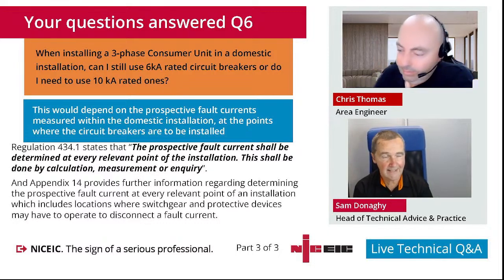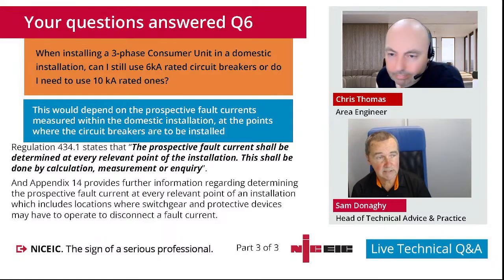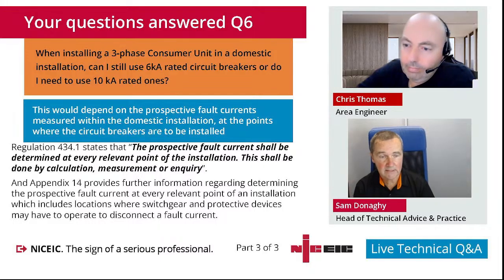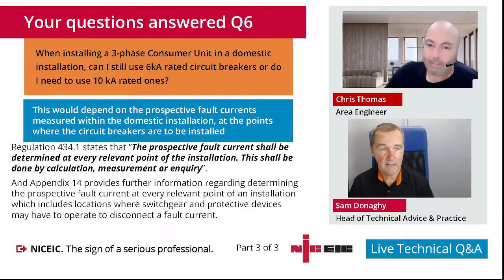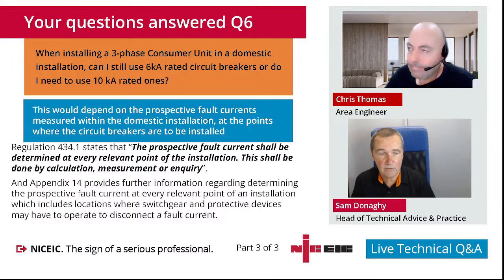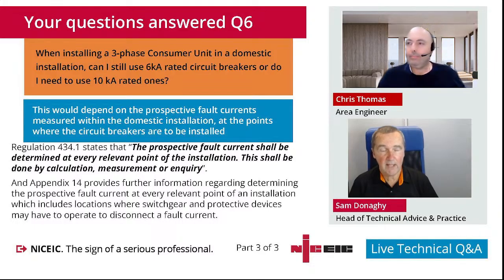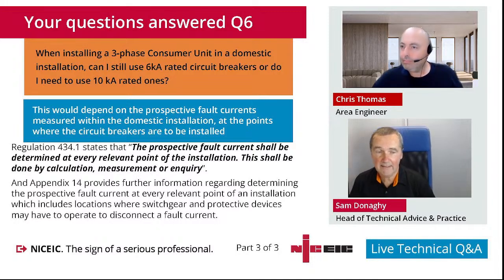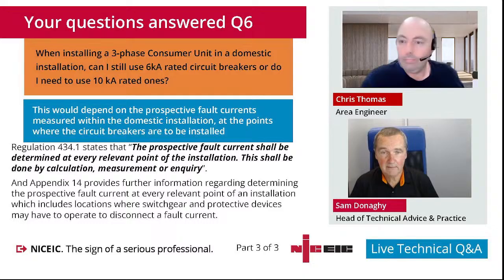But we would suggest that that's documented, either commented on in the installation certificate, in the section on comments on the installation, or in a separate document that you might create to confirm that they have agreed to not have an SPD installed, and then again there's no further comeback. So if at a later date there were to be an issue with an indirect lightning stroke in that vicinity, which caused an issue, and you made them aware of the mitigation that could be done, and they still chose to not do it, then you just want evidence.